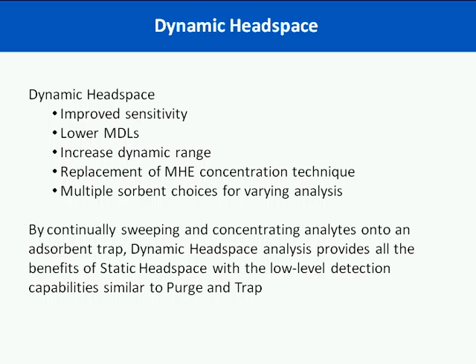With dynamic headspace, we can offer improved sensitivity, lower MDLs, and increased dynamic range. While we're able to see PPM levels with a static analysis, we're able to see PPM and PPB levels with a dynamic headspace analysis. Dynamic headspace analysis is also a great replacement for multiple headspace extraction techniques. There are multiple sorbent choices for varying analysis. With headspace, you're continually sweeping and concentrating those analytes onto that absorbent trap — this is what's going to help with your improved sensitivity and lower MDLs.